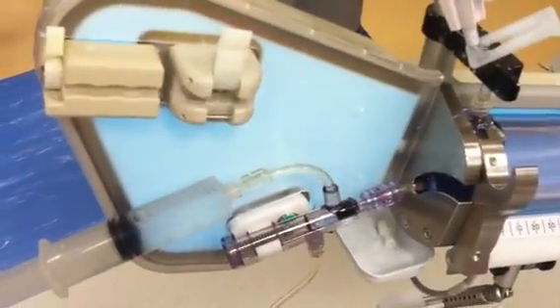Then, my technique is to come back here and do a little quick purge. So as soon as I hit this, you'll see what happens here. Bam. It's ensuring that that entire system, from your bag all the way through the transducer, up to this point here, is air free, and then you'll connect here. You'll put all your tubing through, and it'll be good to go.